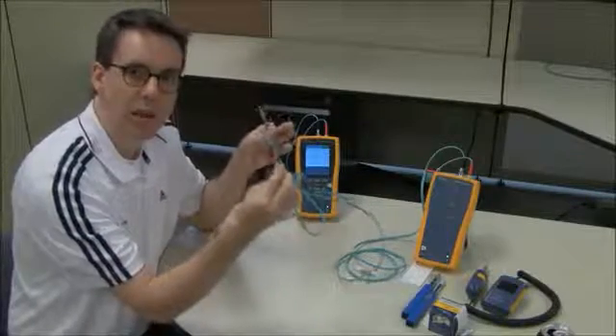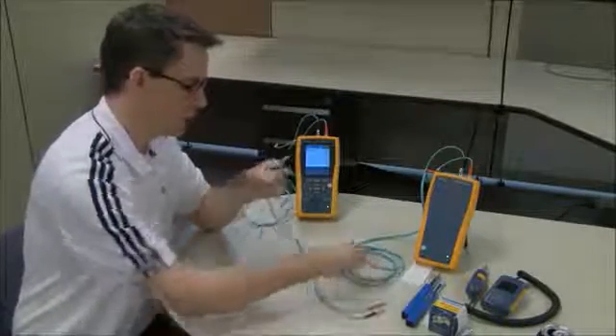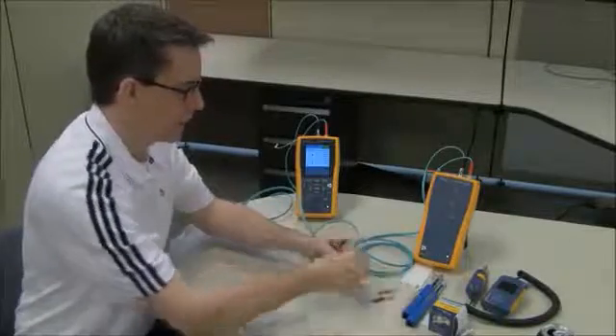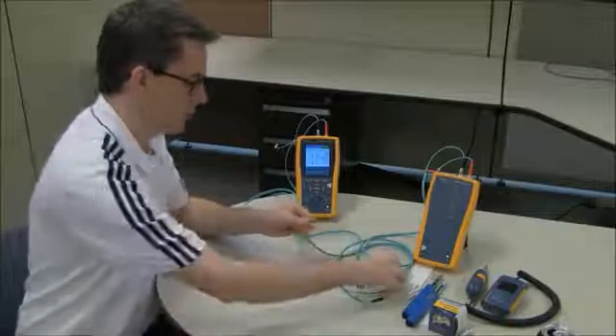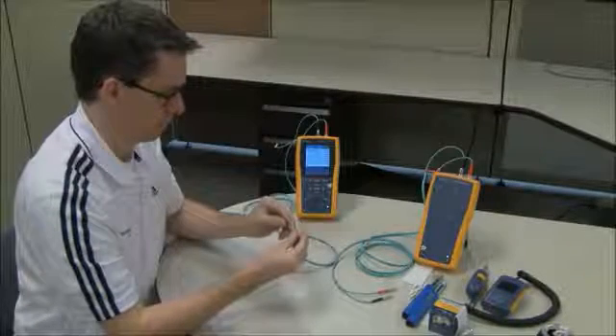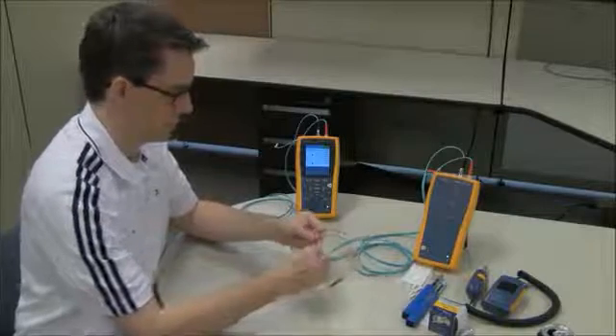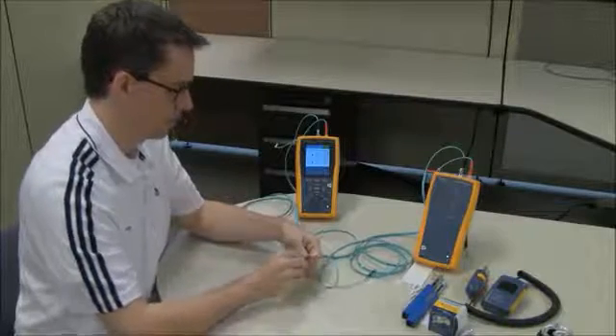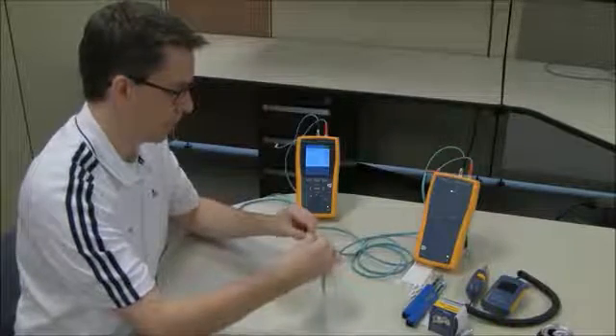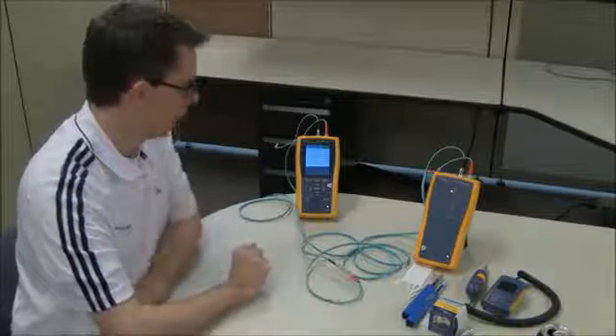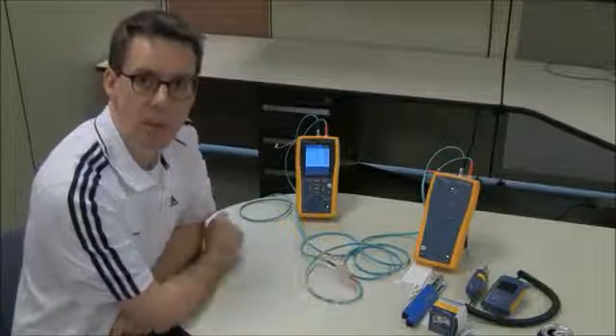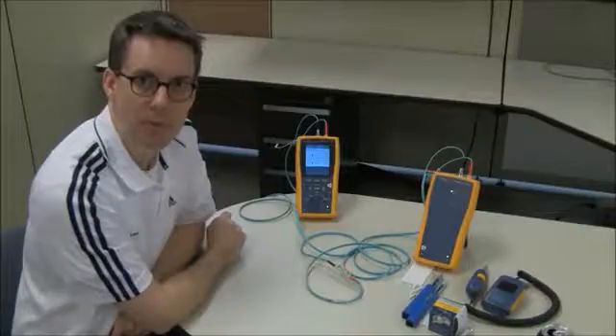The problem is, we don't actually know how good these cords are. So, before you do that, take an LC bulkhead adapter and connect the main and remote units together. Of course, red goes to black, and black goes to red. And, again, if I've done this right, I'll hear a chirp. Then, what I'm going to do is, I'm going to run an auto-test to see what the loss is here. And, I want this to be better than 0.1 dB, if possible. Let's do that now. Okay, so let's run an auto-test.